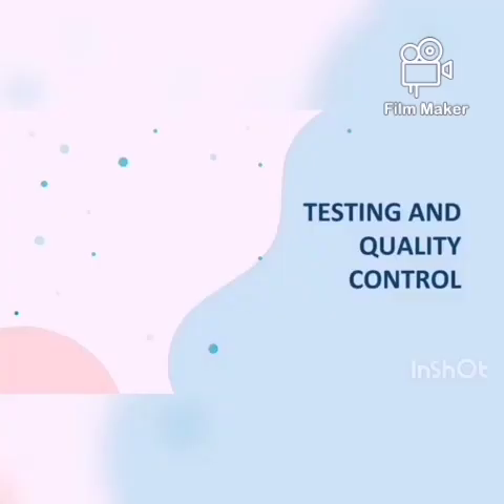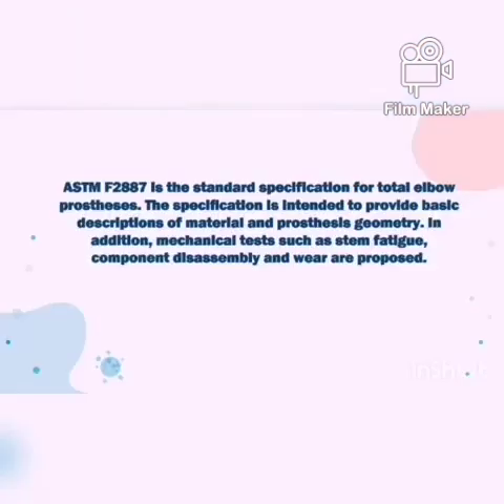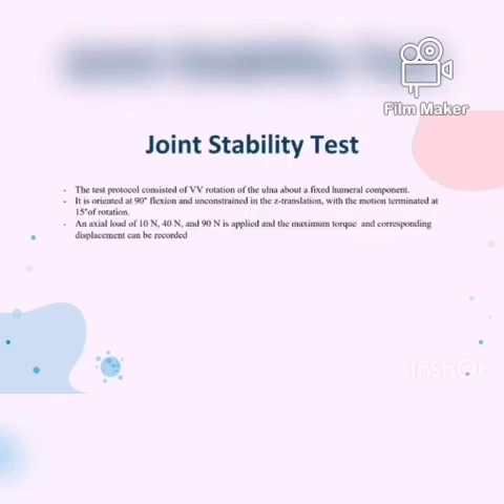Now that we are done with effects of parameters, let's move to testing and quality control. The standard specification for total elbow replacement is ASTM F2887. The specification is intended to provide basic descriptions of material and prosthesis geometry. To make sure the implant is working well, a few tests need to be done.